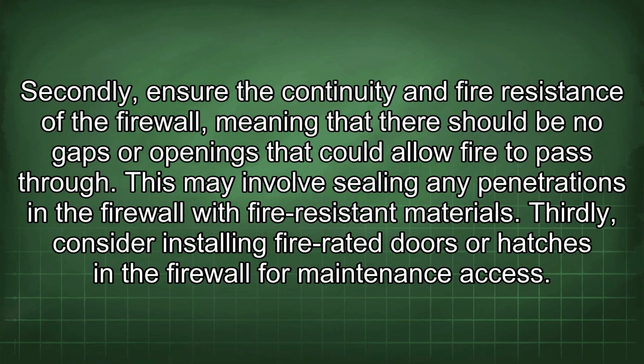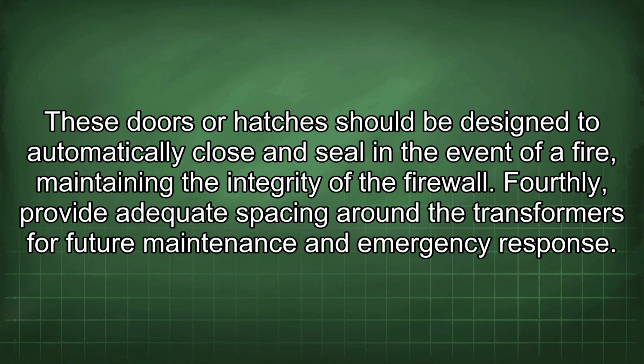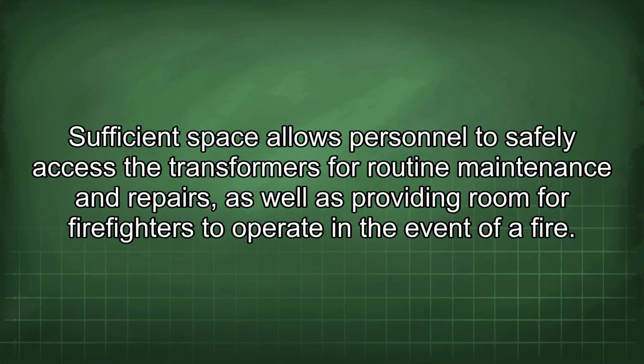Thirdly, consider installing fire-rated doors or hatches in the firewall for maintenance access. These doors or hatches should be designed to automatically close and seal in the event of a fire, maintaining the integrity of the firewall. Fourthly, provide adequate spacing around the transformers for future maintenance and emergency response. Sufficient space allows personnel to safely access the transformers for routine maintenance and repairs, as well as providing room for firefighters to operate in the event of a fire.